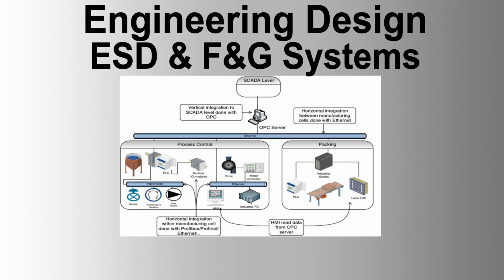Software requirements. 1. Configuration and flexibility. The ESD F&G system software must be configurable to meet all specified functional requirements. The software must allow for online modification without requiring system shutdown or interrupting ongoing processes.